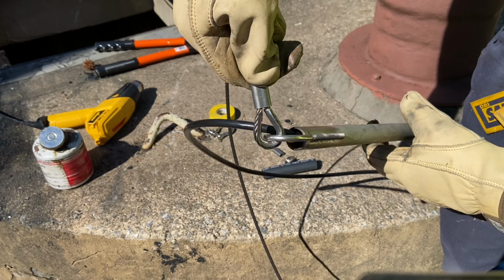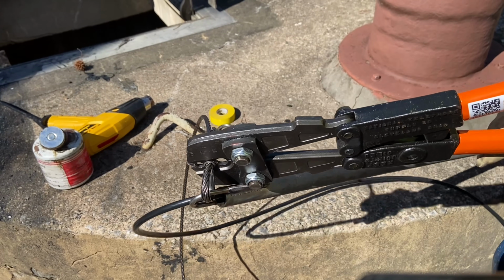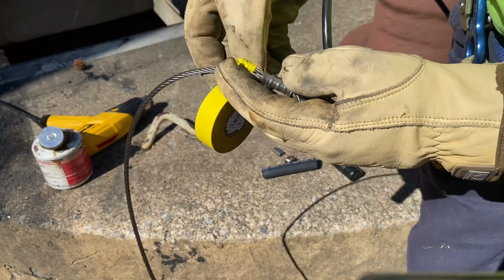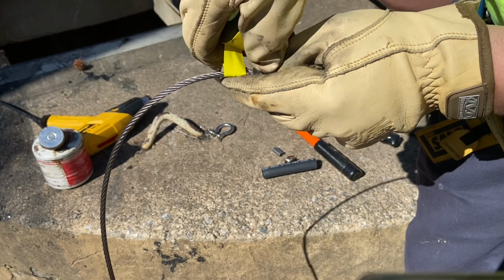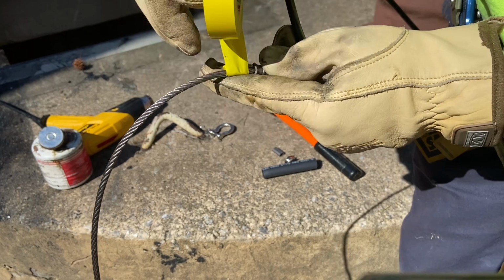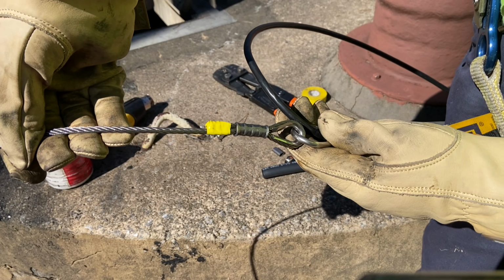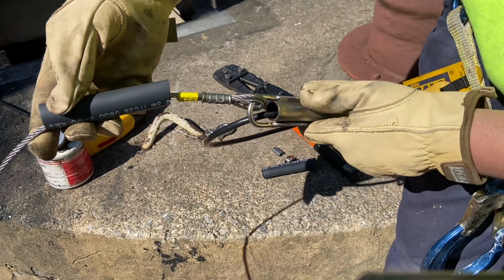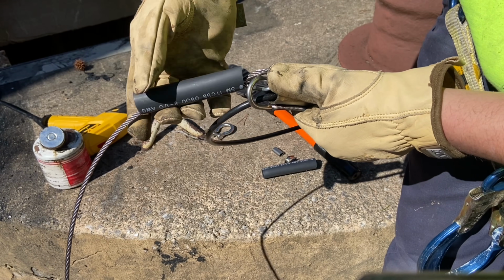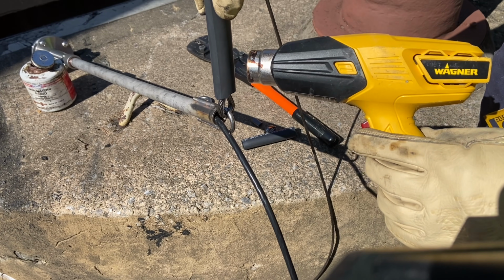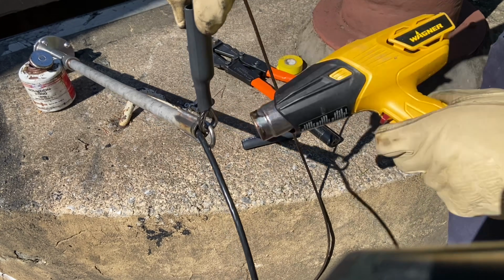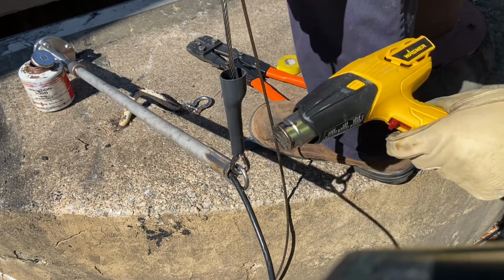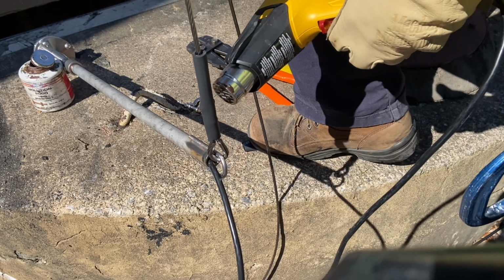And from there, the electrical cable just gets zip tied in whatever increment I feel like that day, all the way up the stainless cable until the top. And at the top, we have a 2-foot piece of chain hanging there, and that chain is so we can adjust the transducer up and down in about 1-inch increments. So we'll start in the middle, and then that gives us plenty of adjustment just in case something changes or we mess up. Which is impossible, of course. Of course!